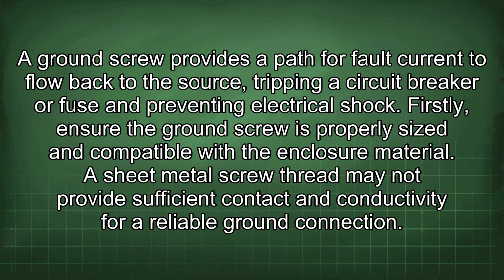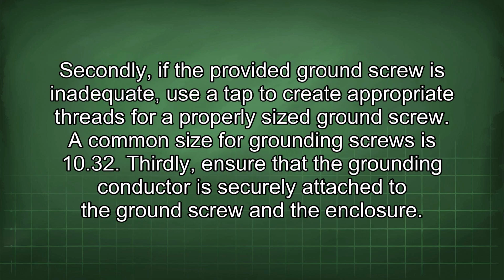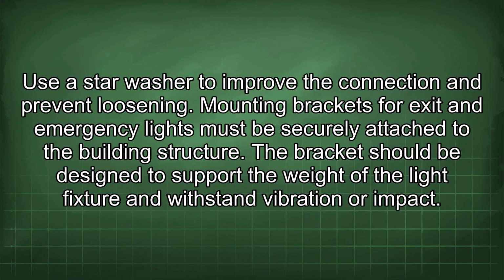Firstly, ensure the ground screw is properly sized and compatible with the enclosure material. A sheet metal screw thread may not provide sufficient contact and conductivity for a reliable ground connection. Secondly, if the provided ground screw is inadequate, use a tap to create appropriate threads for a properly sized ground screw. A common size for grounding screws is 10-32. Thirdly, ensure that the grounding conductor is securely attached to the ground screw and the enclosure. Use a star washer to improve the connection and prevent loosening.